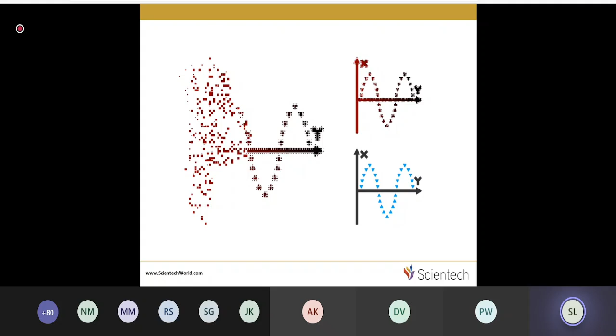So we need a true RMS 5.5 or 6.5 digit multimeter to have better resolution. What does 3.5 digit mean? It means you have 3 complete digits on your display. The display digits can show 0, 1, 2, 3, 4, 5, 6, 7, 8 as well as 9, so they vary from 0 to 9. But the fourth digit, the MSB, will vary only between 0 and 1. So this multimeter will count from 0000 to 1999. That means it is a 2000 count.